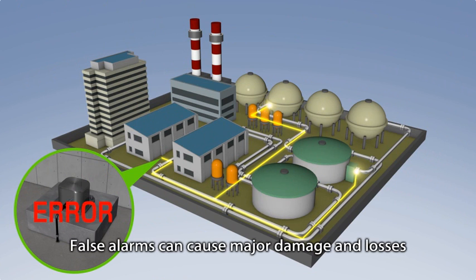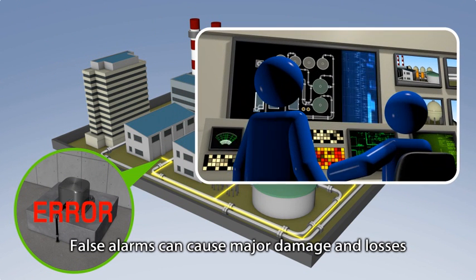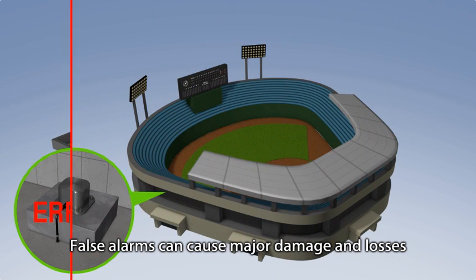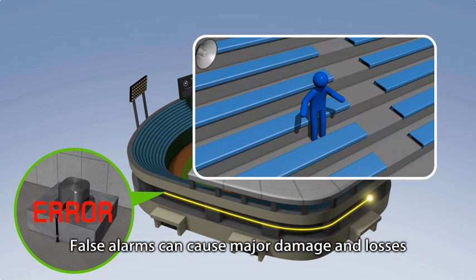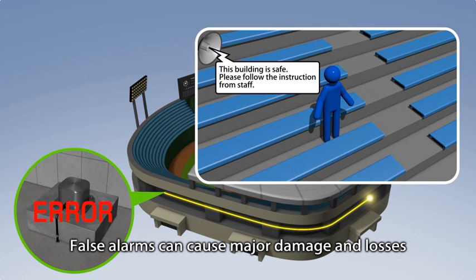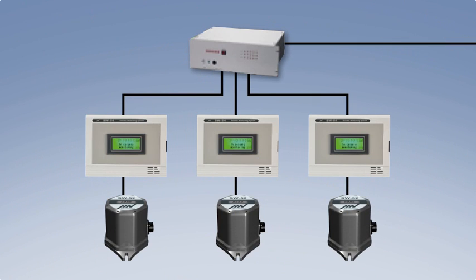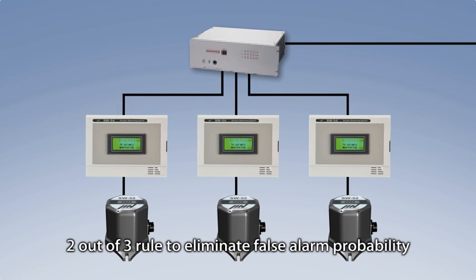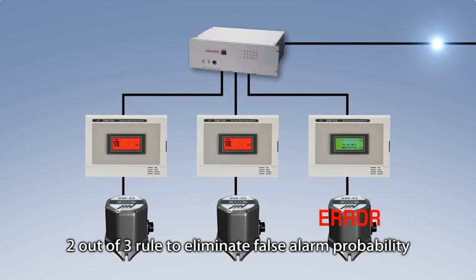False alarms are common problems for early warning systems and poor quality earthquake sensors. A false alarm due to sensor malfunction may lead to premature halting of operations and can cause major losses or even physical damages. A 2 out of 3 rule is necessary for important equipment to avoid false alarms due to malfunctioning. In this rule, the system does not activate controls unless 2 out of 3 sensors detect vibration.